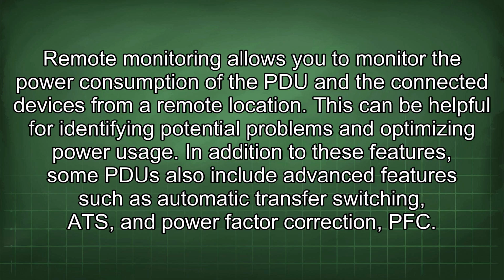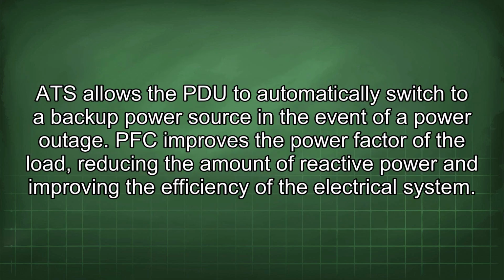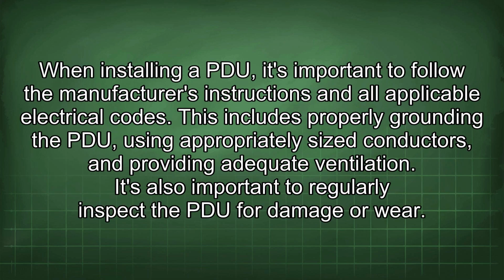In addition to these features, some PDUs also include advanced features such as automatic transfer switching (ATS) and power factor correction (PFC). ATS allows the PDU to automatically switch to a backup power source in the event of a power outage. PFC improves the power factor of the load, reducing the amount of reactive power and improving the efficiency of the electrical system. When installing a PDU, it's important to follow the manufacturer's instructions and all applicable electrical codes.